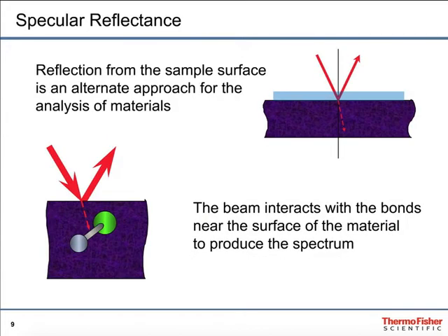In specular reflectance, the sample is placed on a reflective surface. In the cartoon in the upper right corner, you see the light blue film laid on top of the darker surface. The IR beam passes down through the film, reflects off the surface, back through the film, and out, interacting with the sample twice. This is a very good technique for thin films and thin layers on surfaces when the surface is reflective, and the IR beam reports on the bonds near that surface to produce the spectrum.